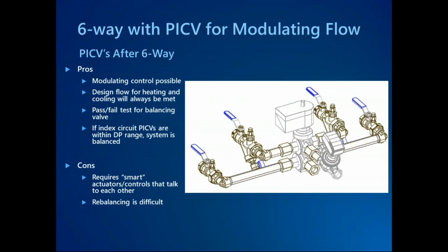One way of helping to simplify that is to actually provide the pressure independent control valve on the dual temperature zone portion of the 6-way assembly. Advantages are all the same as before. You're getting that modulating control that you were looking for. Balancing is relatively easy. You can field adjust max flow to a degree. The con really is that the actuator for the PICV has to be what we call a smart actuator, and has to talk back to our 6-way control valve.